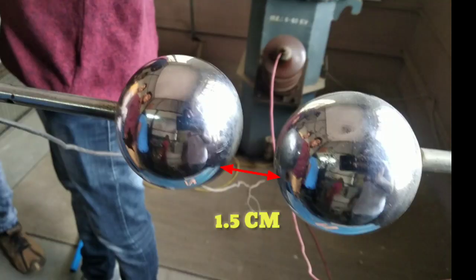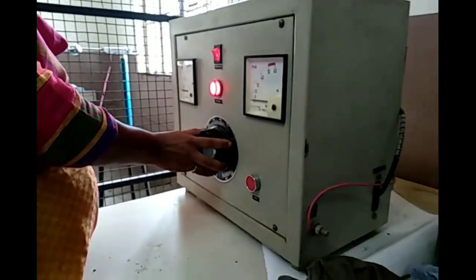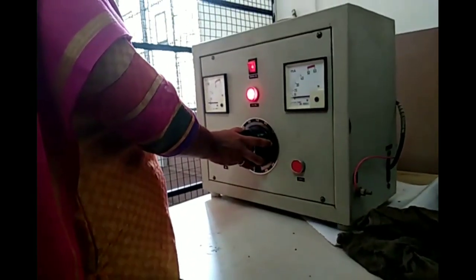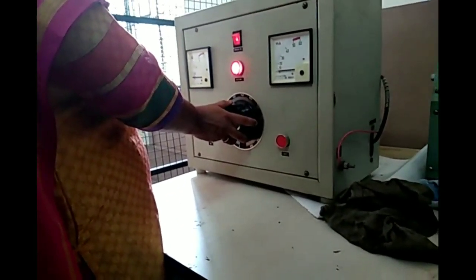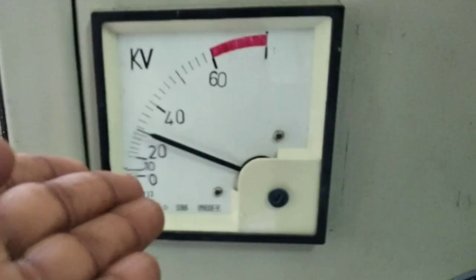Set distance between two sphere gap is 1.5 centimeters. Now increase voltage up to breakdown voltage. Breakdown voltage is 30 kilovolts when distance is 1.5 centimeters of sphere gap.